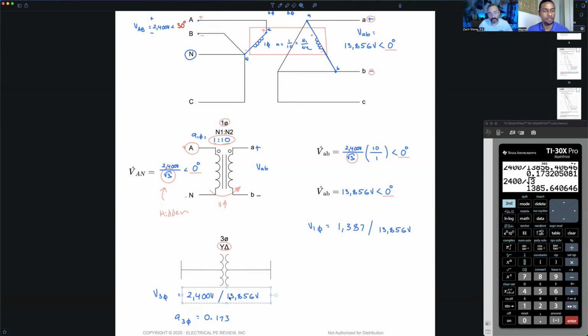Using this voltage ratio, if I apply 2400 volts primary, what's my secondary line voltage going to be? 13,856. When you're given your three-phase voltage ratio, any hidden square root of threes are automatically baked into that number. They're automatically included. You don't have to worry about them.